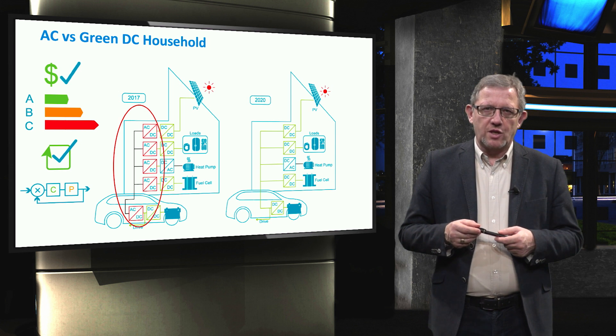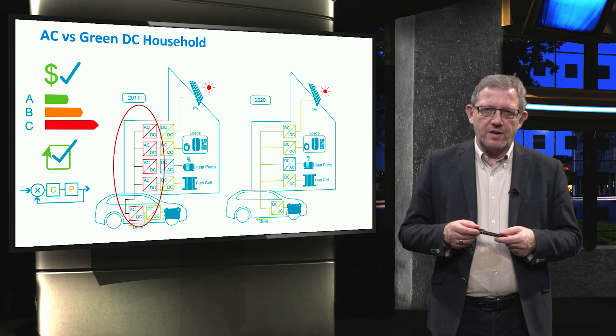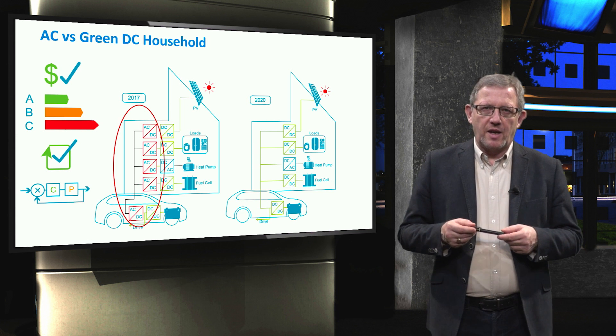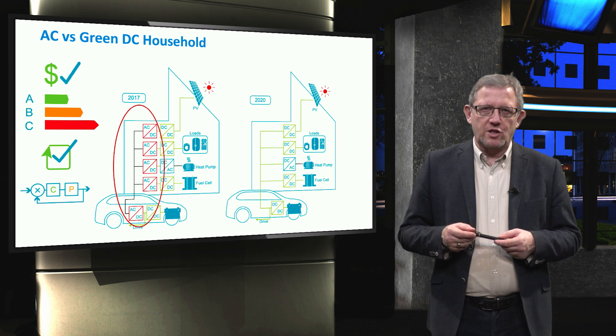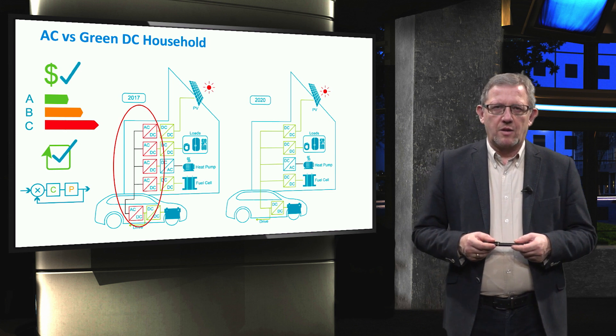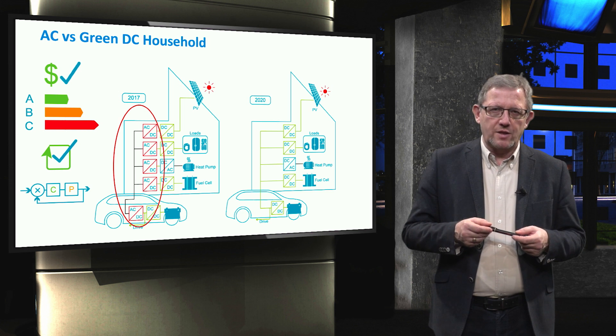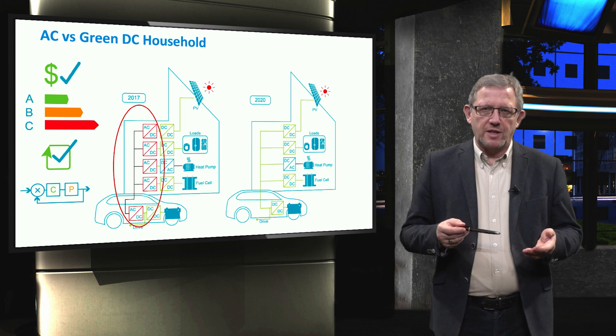Note that voltage is typically seen as a local variable, while frequency in AC is a global variable. In an AC system, the frequency is noticeably affected only when the unbalance is very high at the system level. In a DC microgrid on the other side, you will see immediately the drop of voltage when unbalance happens, and in this way it is possible to act directly on the control. Note that the control system's complexity is high in AC due to the need for monitoring two variables, voltage and frequency. However, it is much simpler in DC, where only DC voltage has to be monitored.